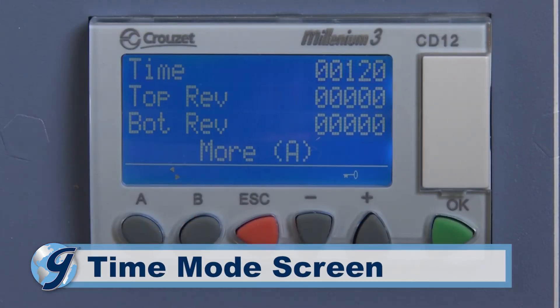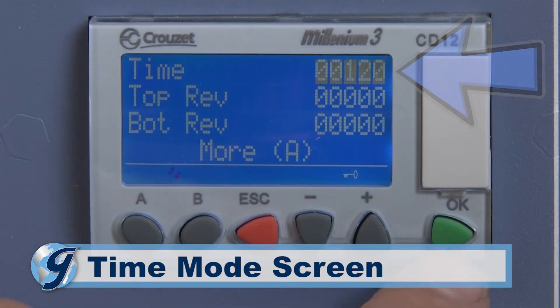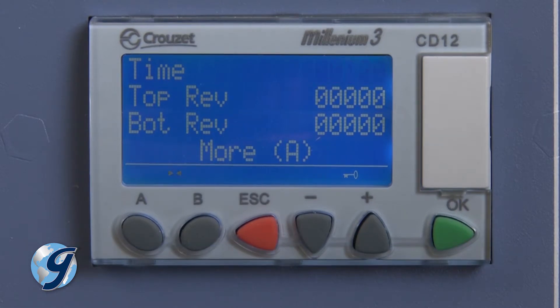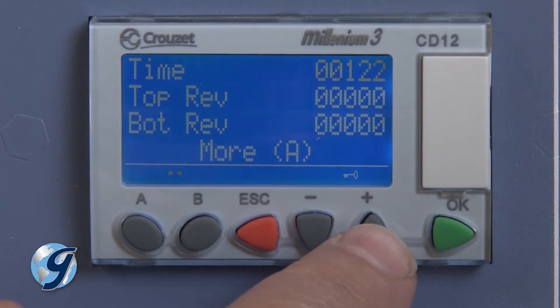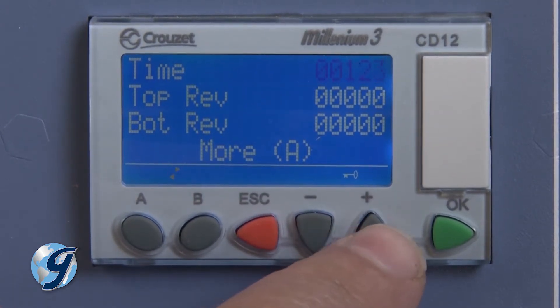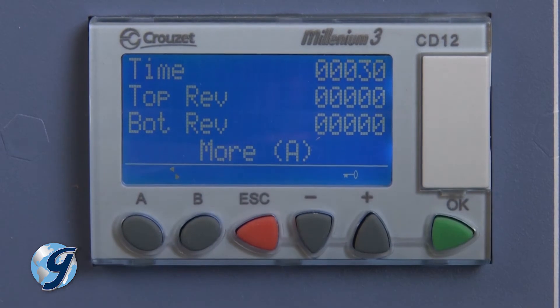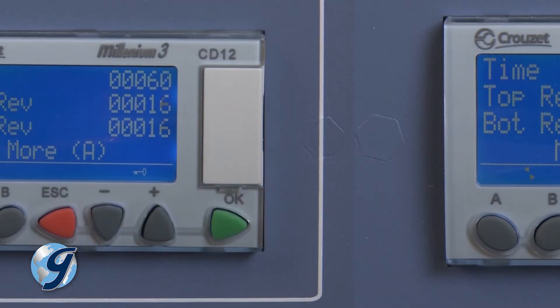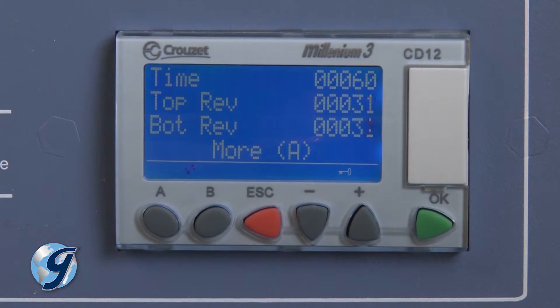In selecting the time mode, the timeline will indicate the set point in whole minutes. To change the set point, press OK and the time value will begin to flash. Adjust the set point using the plus and minus buttons; as the buttons are held down, the rate of change will become faster. Once the desired value is displayed, press OK to save. Now you are ready to begin your test. The next two lines display current test revolutions for the top and bottom jars and are updated every second. Revolutions will reset to zero and begin counting once the start button is pressed.